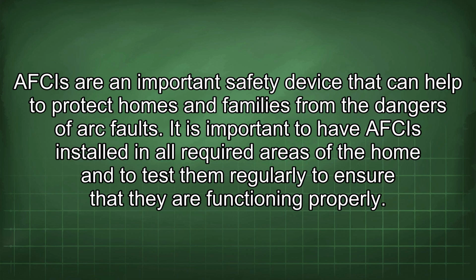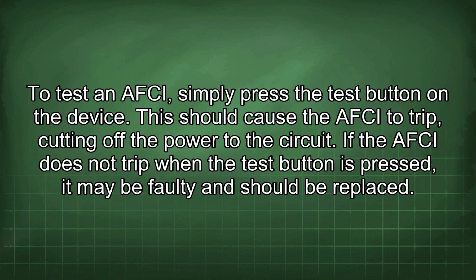It is important to have AFCIs installed in all required areas of the home and to test them regularly to ensure that they are functioning properly. To test an AFCI, simply press the test button on the device. This should cause the AFCI to trip, cutting off the power to the circuit. If the AFCI does not trip when the test button is pressed, it may be faulty and should be replaced.